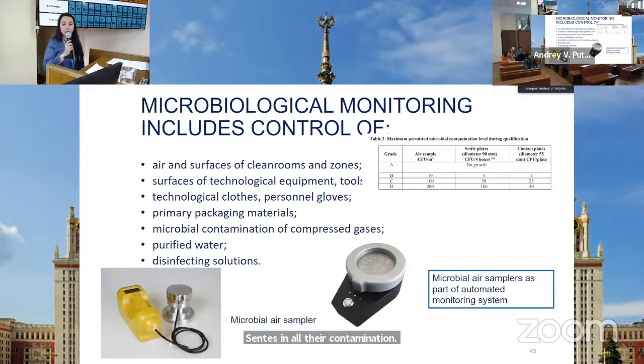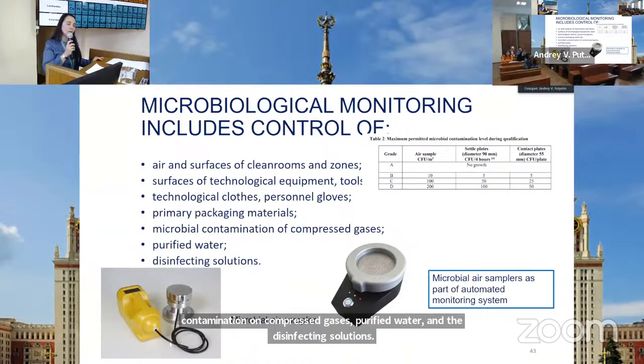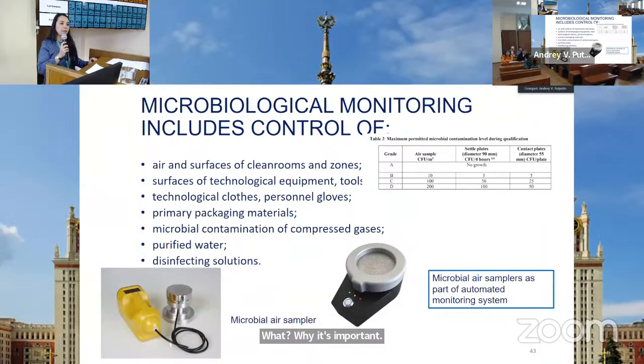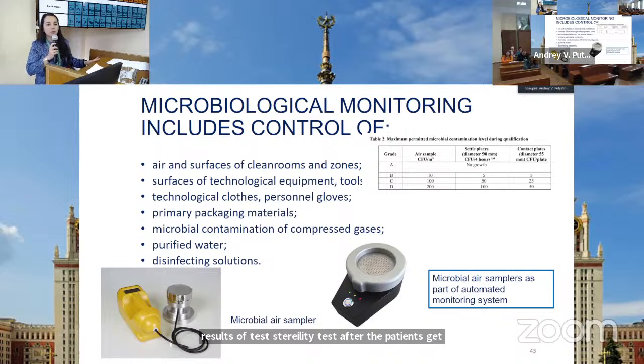For the control of microbial contamination inside your production facility, we can use different instruments, such as microbial air samplers. The requirements of the microbial monitoring include air, surfaces of clean rooms and zones, equipment, clothes, personnel gloves, primary packaging materials, microbial contamination of compressed gases, purified water, and disinfecting solutions. Why is it important? As I said, we can get the results of the sterility test after the patients get the radiopharmaceuticals. In that case, microbial control is a very important part of radiopharma production sites.